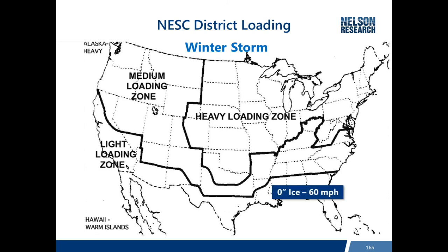Light loading starts with zero ice and a 60 mile-per-hour wind — which is why the loading in the light district might be greater than in the medium district. Heavy loading has a half inch of radial ice, which adds an inch to the diameter of the wires, and then applies a 40 mile-per-hour wind.